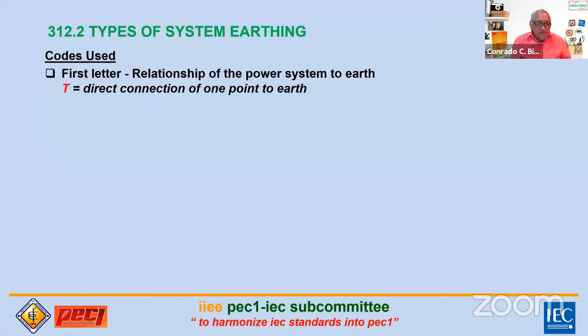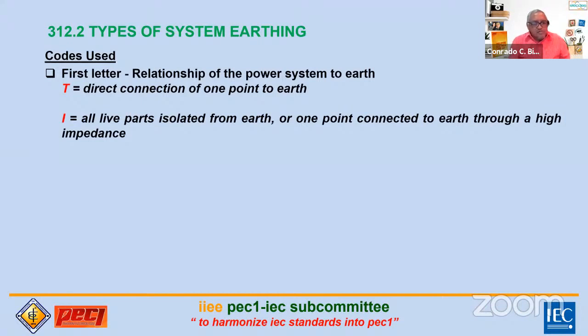The codes use a first letter for the relationship of the power system - this is the transformer, where our source of supply comes from. If there's a direct connection of one point to earth, that's called T. If you connect one point of the source to earth, probably the neutral or one of the lines, you make it earthed - that's T, from the French word 'terre'. The second one is I - all live parts isolated from earth, or one point connected to earth through high impedance, like a series resistor or transformer impedance.